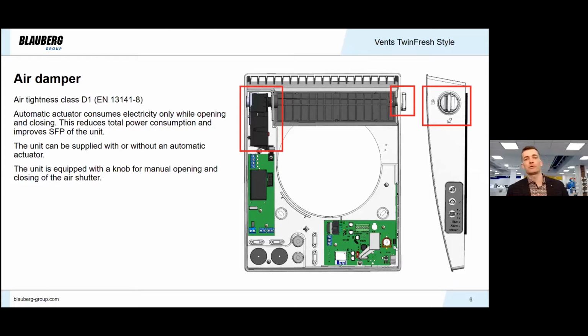Little bit of information about air damper built into the unit. So the new construction of air shutter guarantees maximum air tightness, D class according to EN 13141-8. Automatic actuator consumes electricity only while opening and closing. This reduces total power consumption and improves specific fan power of the unit. The unit can be supplied with or without an automatic actuator. At the right of the unit you can see a knob for manual opening and closing of the shutter. As you can see, the grill is located at the top of the unit. This directs supply air stream upwards, which is beneficial because the user will not feel drafts or cool air spread along the floor.